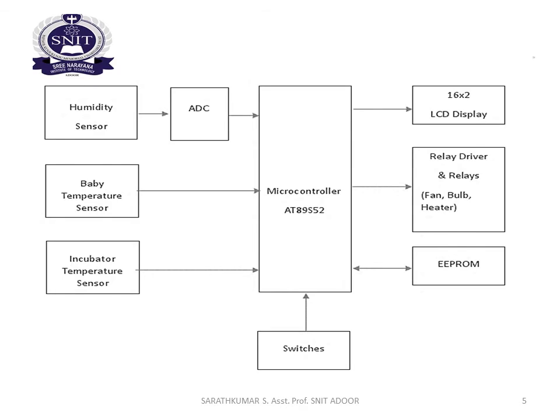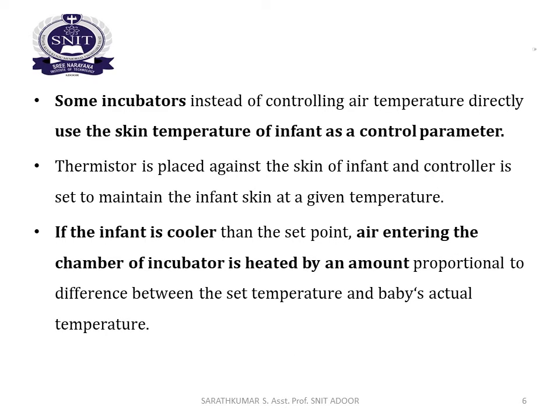Some incubators, instead of controlling air temperature directly, use the skin temperature of the infant as a control parameter. A thermistor is placed against the skin of the infant, and control is set to maintain the infant's skin at a given set temperature.